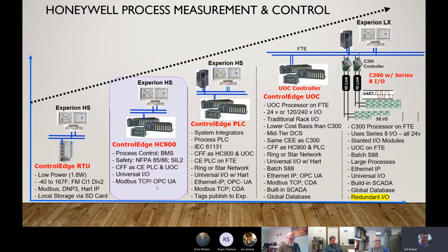So for third-party devices that you want to communicate to the HC900 system to share information back and forth, it allows a real nice versatile communication path to be able to do that. In many applications that utilize that type of communication protocol, we're taking the HC900 and communicating to either the Honeywell paperless strip chart recorders, circular chart recorders, actuators, in some cases transmitters.